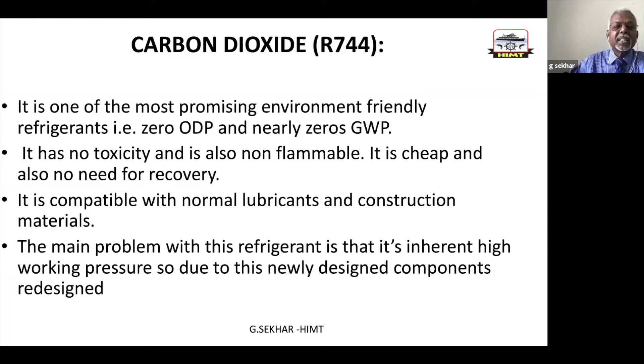And on the compressor discharge side, what you are having? You are having a discharge valve, and after the discharge valve, discharge pipes, and you have an oil separator, and the pipelines lead to the condenser. And at the condenser, what is going to be the pressure? It's going to be the same pressure. So condenser, liquid receiver, then from the liquid receiver right up to the expansion valve, it's what we call the high pressure side. Now on the high pressure side, 76 bar is practically not possible. So that's why we are not using carbon dioxide. Of course, shore side you can see ammonia related or even carbon dioxide related, but you can call carbon dioxide an eco-friendly refrigerant.